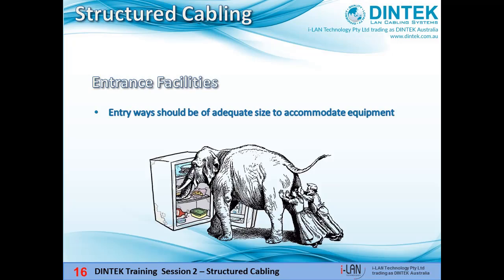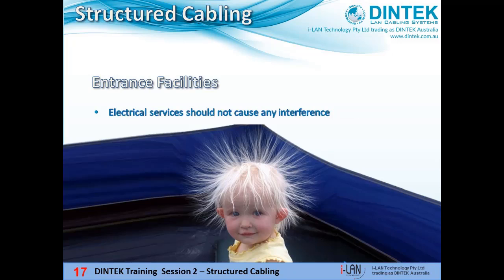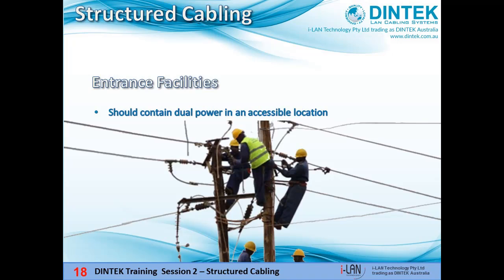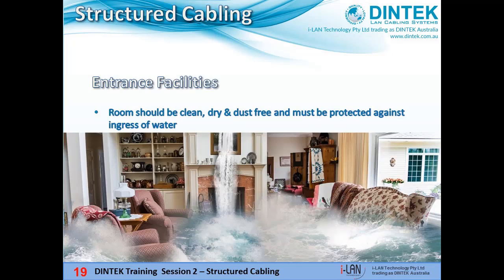The entryways should be of adequate size to accommodate equipment — more something to be considered at the design stage. There should always be consultation with the phone carrier and whoever's installing the backbone cabling to make sure we know what needs to fit in there and how we future-proof ourselves, for example, throwing in an extra conduit with a drawstring while we've still got an open trench. Electrical services should not cause any interference — the last thing we need is buzzing phone lines or unreliable data links. There should be a dual power outlet in an accessible location. And the room should be clean, dry, dust-free and protected against water ingress.